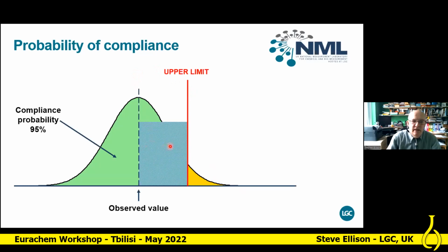Let's put some gap between the specification, the edge of the specification, and the edge of the acceptance range. So we're now defining a smaller acceptance range, and that gap, this grey thing here, is called a guard band. And that's a standard way of controlling risks of false declaration. In this particular case, this controls the risk of a false declaration to 5%.